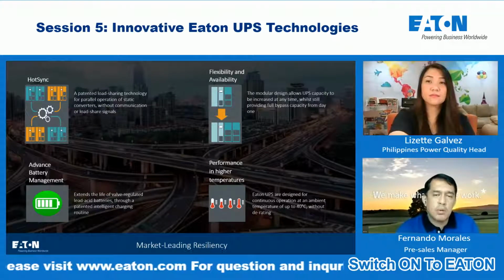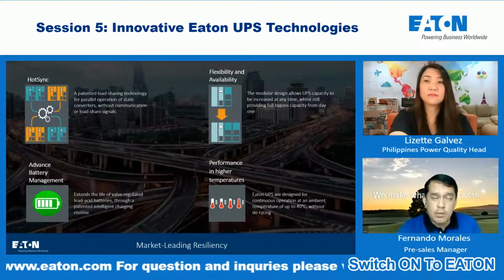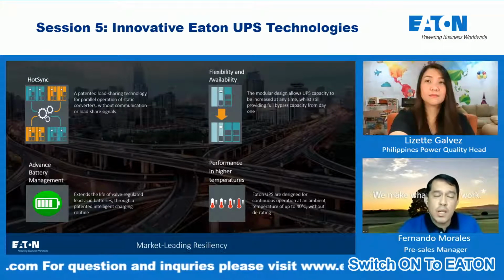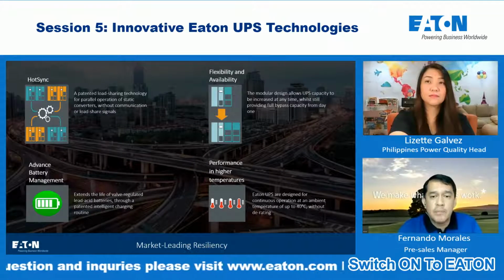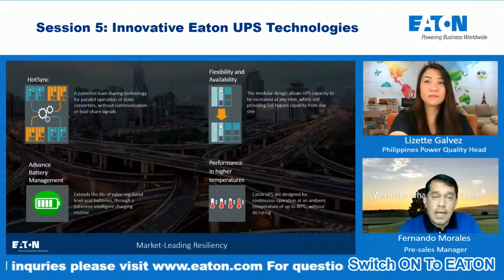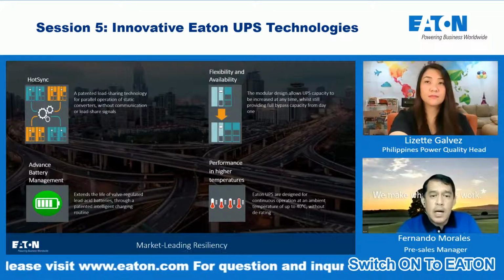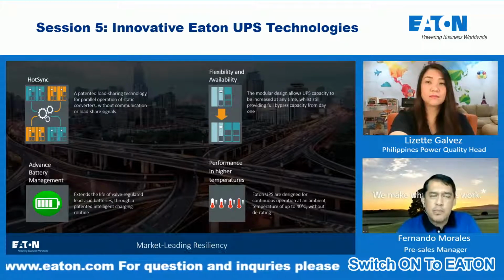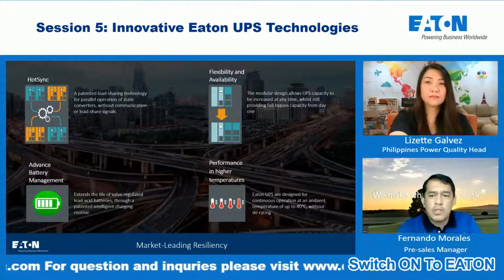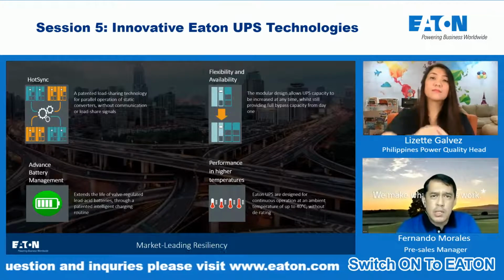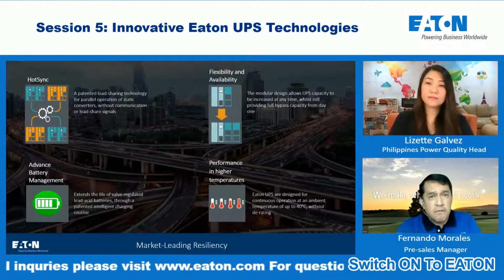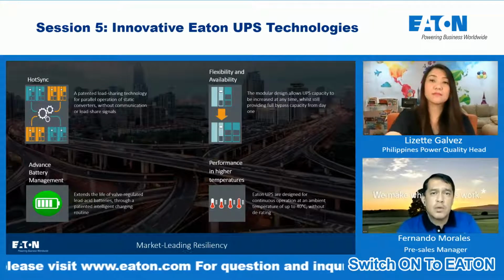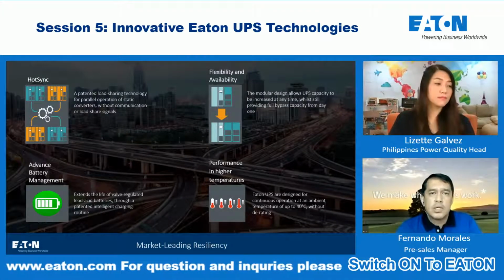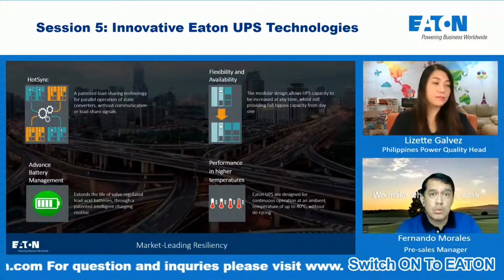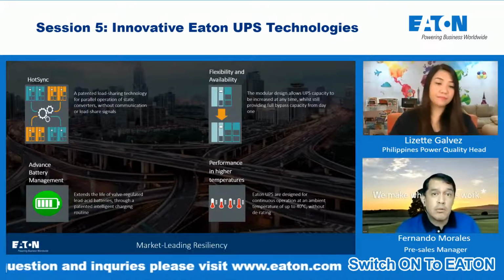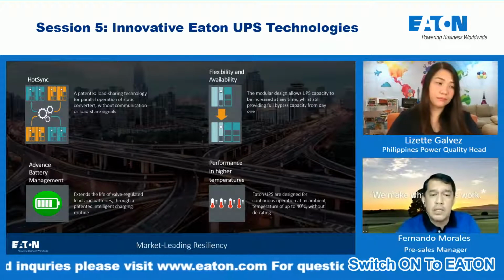The second reason, which is the most common reason why we parallel a UPS, is because the customer wants to further increase the availability of their critical system. By having a redundant or multiple redundant backups, we prevent downtime due to power disturbances. For example, we all know that a single UPS may fail eventually. If you only have a single UPS and experience a failure, the critical loads of the customer will be exposed to the utility power and to different elements of power disturbances.